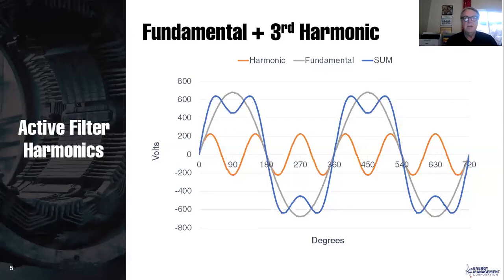This is not a sine wave. If you look at the dark blue, you see it kind of goes up. It has a little dip in the middle and comes down. Now, if somebody were to bring me in and say, hey, look at our current or look at our voltage, what do you think? I would say, ooh, that's not good. You have dirty power. You have corrupt power. You have harmonics. And if they said, well, can you help me fix it? The answer is no. I don't know what to do with that wave shape.